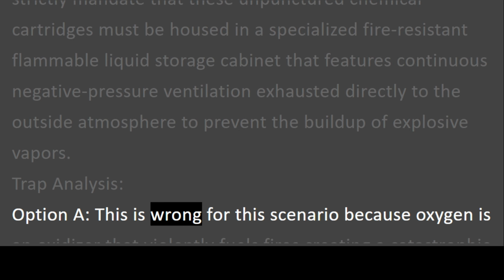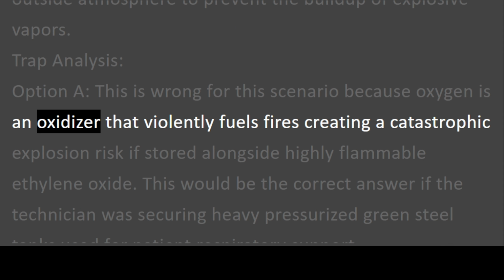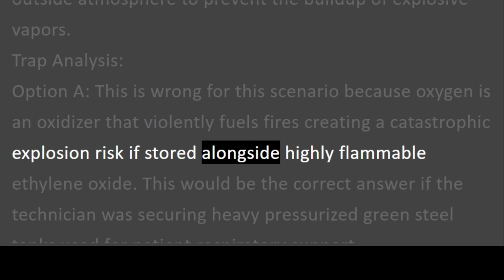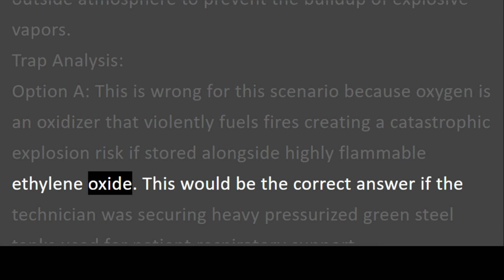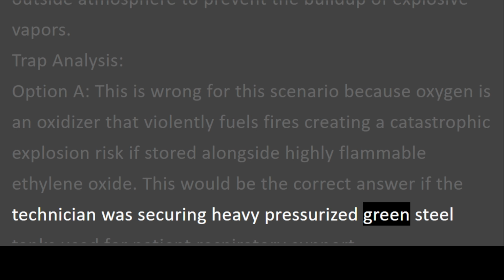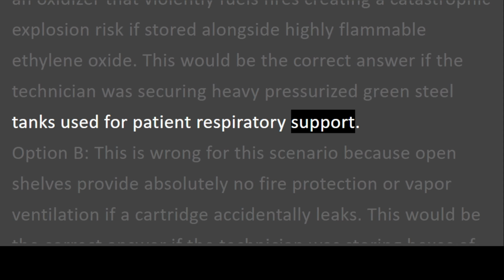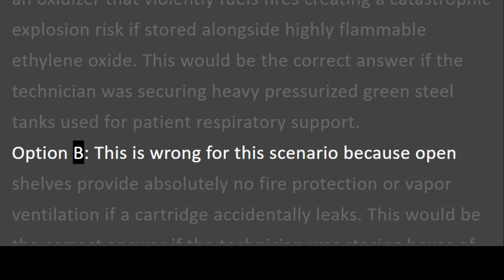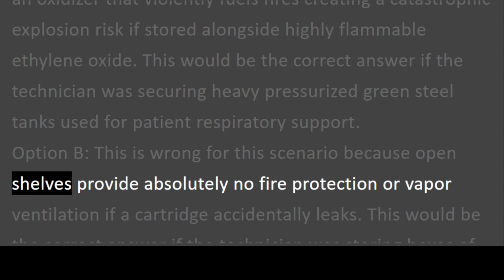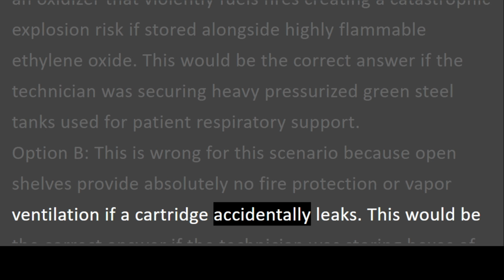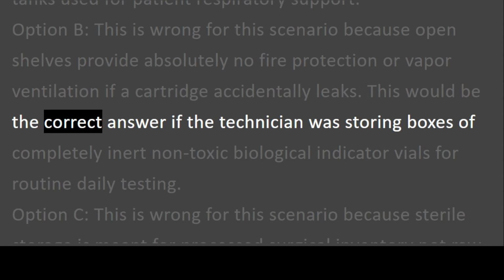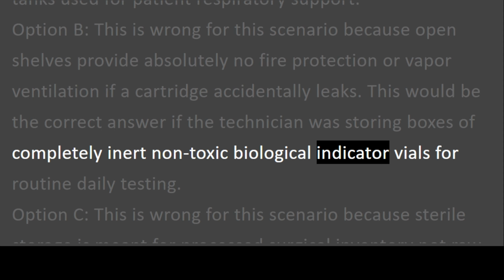Option A. This is wrong for this scenario because oxygen is an oxidizer that violently fuels fires, creating a catastrophic explosion risk if stored alongside highly flammable ethylene oxide. This would be the correct answer if the technician was securing heavy pressurized green steel tanks used for patient respiratory support. Option B. This is wrong for this scenario because open shelves provide absolutely no fire protection or vapor ventilation if a cartridge accidentally leaks. This would be the correct answer if the technician was storing boxes of completely inert, non-toxic biological indicator vials for routine daily testing.